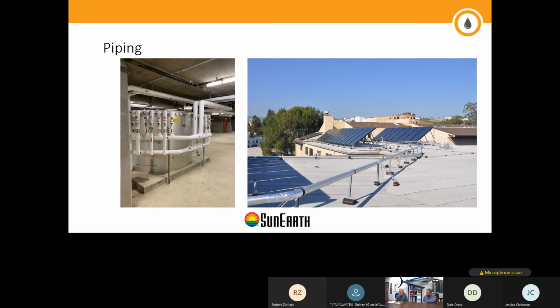This piping does come up with inspectors, and generally the piping for the solar circuit is done by the designers or the installers, and the inspectors generally just assume that that's correct. They're not there to see that the system works. That's your job as the engineer or installer, that you designed it properly. So hopefully you've designed it properly. Sometimes they will, though, ask what's the velocity through the pipe? They'll call you on that, and you may have to do the numbers and produce the flow rates and velocity through the diameter of pipe you're using.